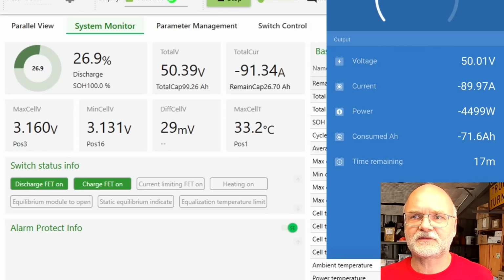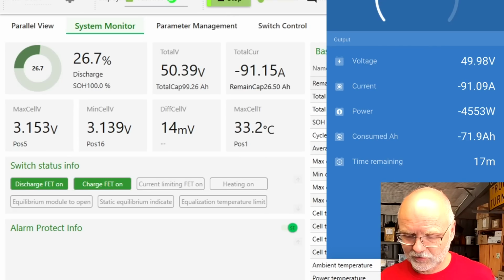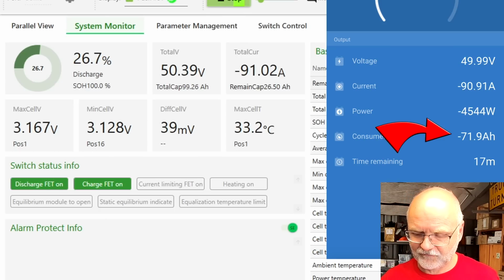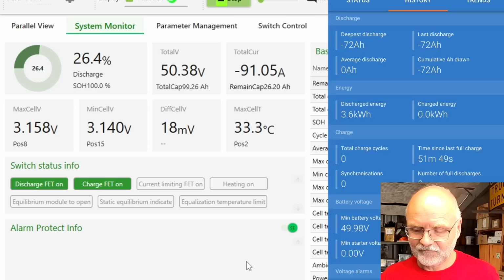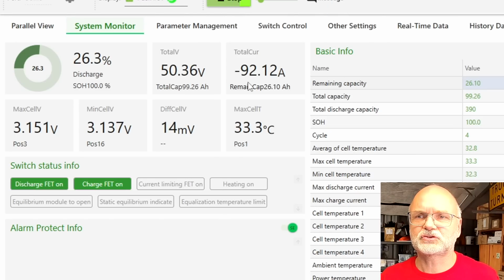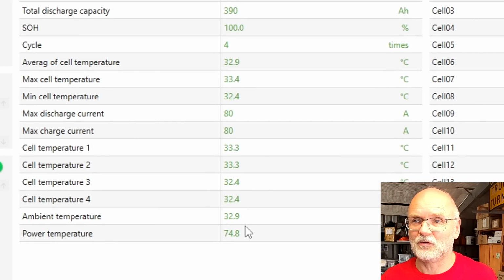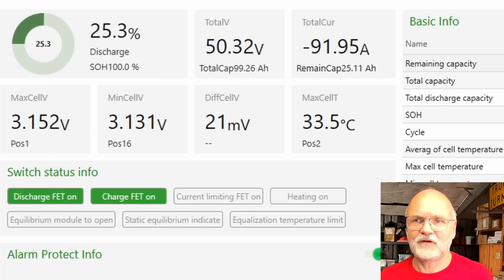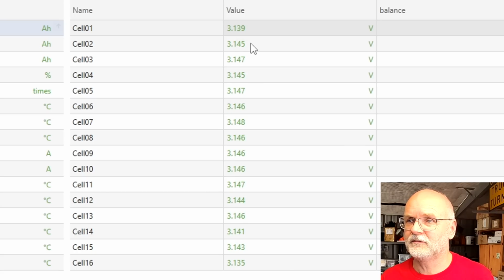And we are now at 27% state of charge. We have pulled 72 ampere hours so far, 3.6 kilowatt hours in 52 minutes. So the voltage is now down to 50.4 volts. We are discharging with 91, 92 amps. And the temperatures, now you can see we are almost at 33 degrees. The BMS temperature has increased to 75 degrees. Wow. Around 25 millivolt deviation we have in average. All cells are above 3.14 volts as far as I can see. So that all looks good. Battery is going strong.